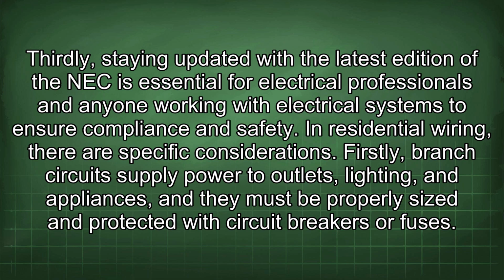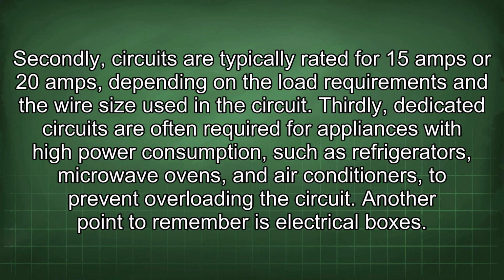In residential wiring, there are specific considerations. Firstly, branch circuits supply power to outlets, lighting, and appliances, and they must be properly sized and protected with circuit breakers or fuses. Secondly, circuits are typically rated for 15 amps or 20 amps, depending on the load requirements and the wire size used in the circuit. Thirdly, dedicated circuits are often required for appliances with high power consumption such as refrigerators, microwave ovens, and air conditioners to prevent overloading the circuit.